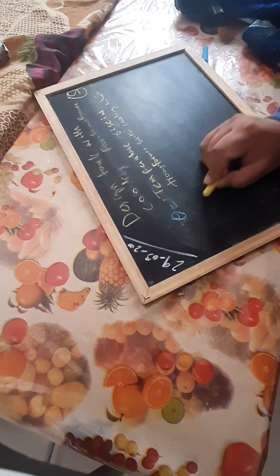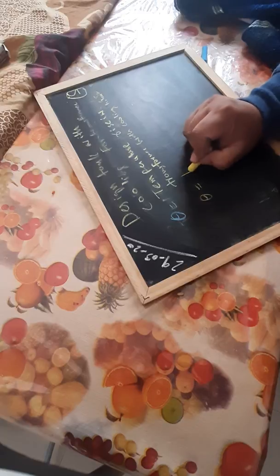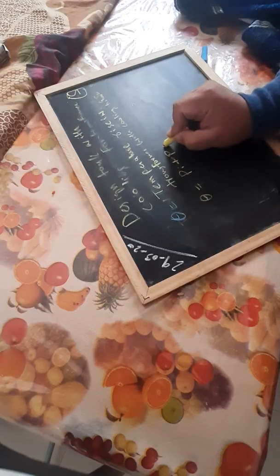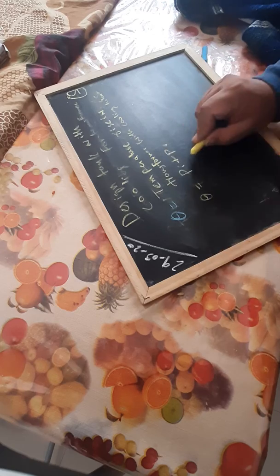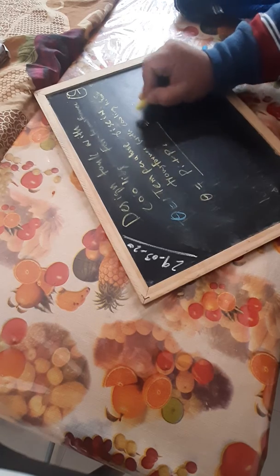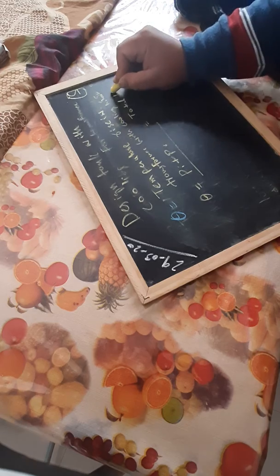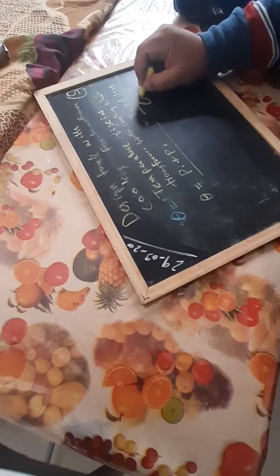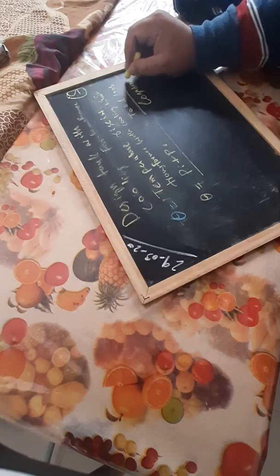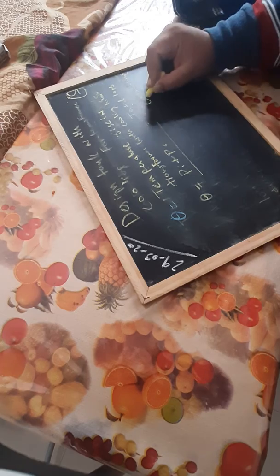So temperature rise theta depends upon the total loss, which depends upon your iron loss and your copper loss in the core. That is, Pi plus P copper divided by your loss dissipated, meaning your total loss divided by your loss dissipated per surface area.